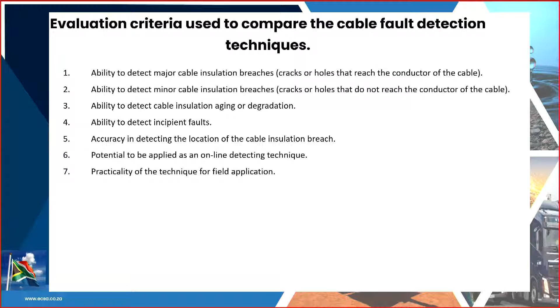Categories 3 and 4 are very important because the technique needs to be able to detect the aging of the insulation as well as the degradation and the ability to detect incipient faults. Last but not least, point 7: we need to know that we can practically apply this method in the field.